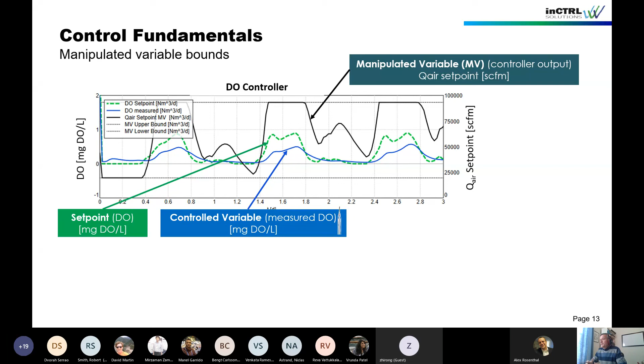Yeah, very important. So if you plot that this way, it's relatively easy to analyze. Okay, so we have a difference between set point and controlled variable. This is the reason. So these bounds are very, very important to look at. They have all kinds of meanings. In this specific case, the maximum airflow is very often defined by the maximum airflow per diffuser. That is a spec these diffusers have, so that you are not impacting the equipment itself.